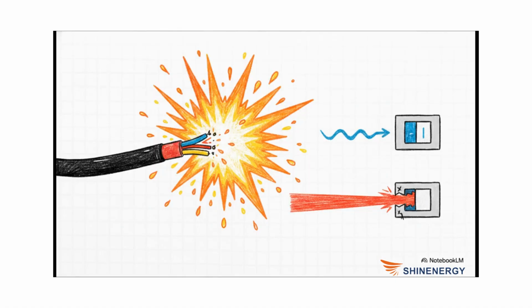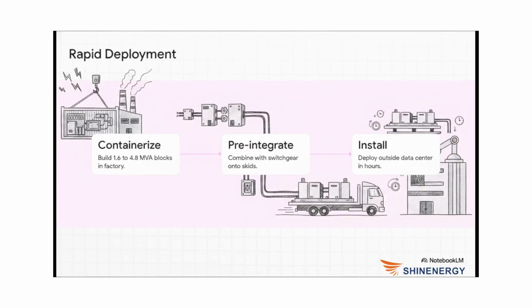However, moving to 800 volts DC introduces some deeply serious and, frankly, kind of terrifying engineering realities that operators absolutely have to respect. Unlike older 48-volt telecom systems where you could safely touch a busbar without much worry, 800 volts is highly, highly lethal. A short circuit at this voltage can cause severe arc flashes, with temperatures hot enough to instantly spew molten copper. Furthermore, AC power inherently has what's called a zero crossing, meaning the voltage naturally drops to zero 50 or 60 times a second, which makes it way easier for breakers to interrupt a fault. High-voltage DC doesn't do that at all, meaning the protection and insulation systems have to be incredibly robust and highly specialized. To manage all of this safely and rapidly, the entire deployment model itself is changing.